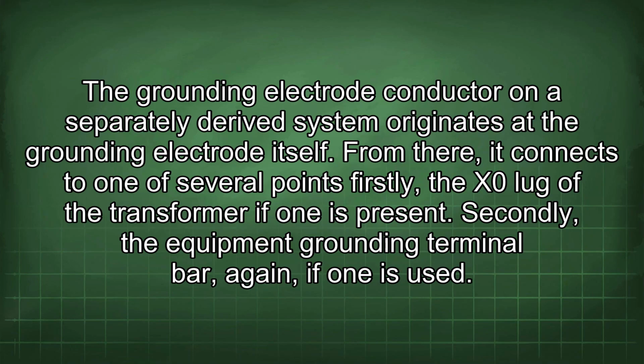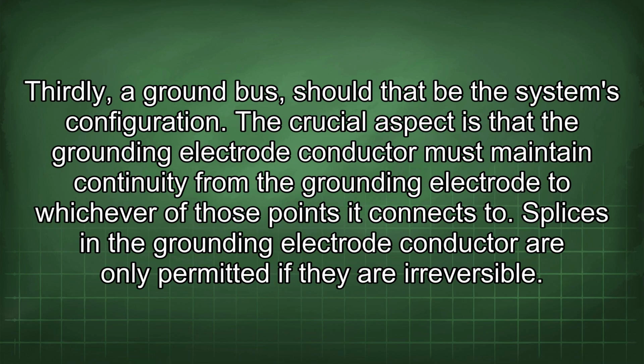The grounding electrode conductor on a separately derived system originates at the grounding electrode itself. From there, it connects to one of several points. Firstly, the X0 lug of the transformer if one is present. Secondly, the equipment grounding terminal bar, again if one is used. Thirdly, a ground bus, should that be the system's configuration. The crucial aspect is that the grounding electrode conductor must maintain continuity from the grounding electrode to whichever of those points it connects to. Splices in the grounding electrode conductor are only permitted if they are irreversible.